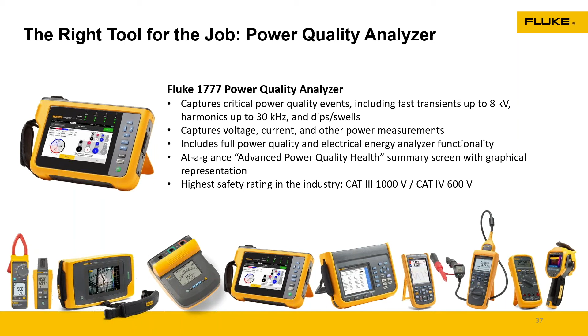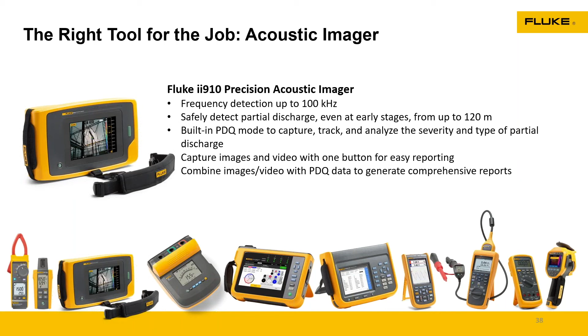Finally, I like to throw in the II910. If you think about all the tools we've talked about, they really help on the solar aspect, whether it's the solar panels, the combiner boxes, all your lines and conductors going back into the inverter, and even after the inverter to the step-up transformer. But once we get into utility-style substations, this is where an II910 can be very effective. It will help determine, at a safe level, if you have partial discharge or key failures happening in that substation.